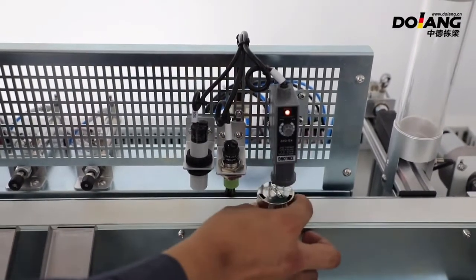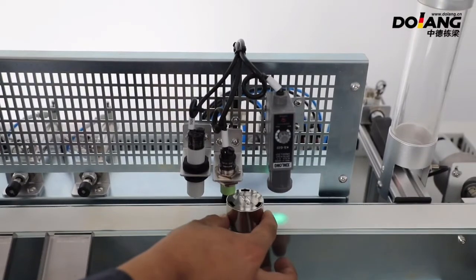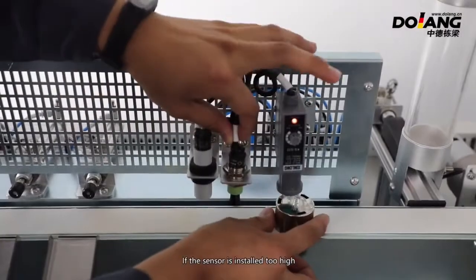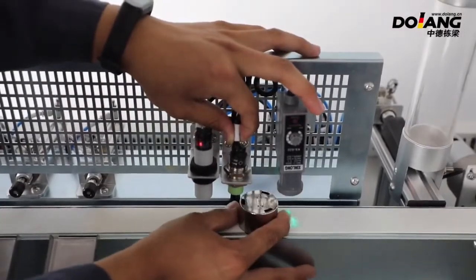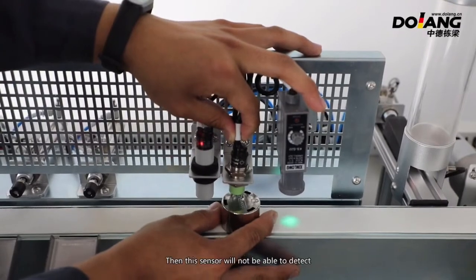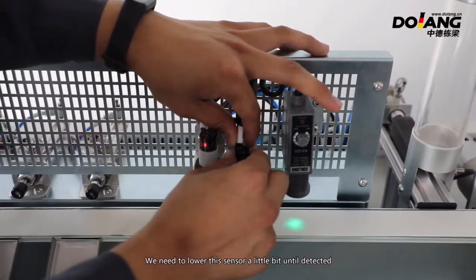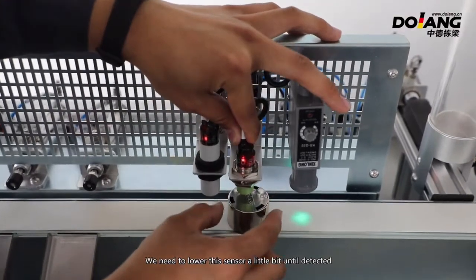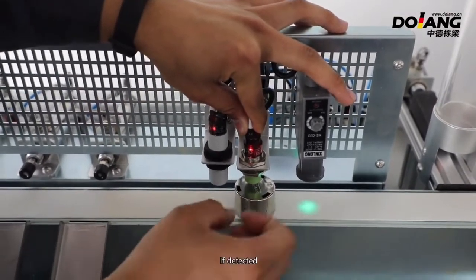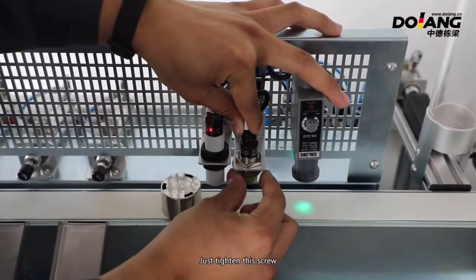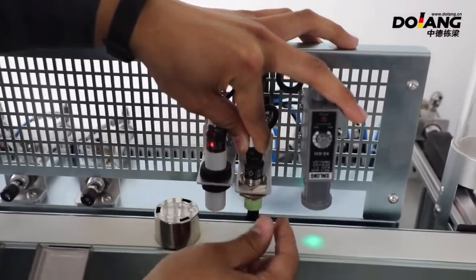How to adjust the sensor? First, put the material block here. If the sensor is installed too high, then this sensor will not be able to detect. How to solve the problem of not detecting the material block? We need to lower the sensor a little bit until detected. If detected, just tighten this screw.